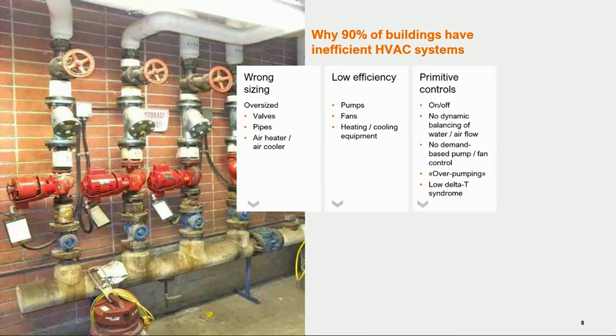When it comes to controls, I call this the primitive controls. We see on-off, if we're lucky, leaking valves, no hydronic balancing in the building, no demand control on pumps and fan control. Overpumping is very common, with water pumped through buildings every day without consumers really needing it.